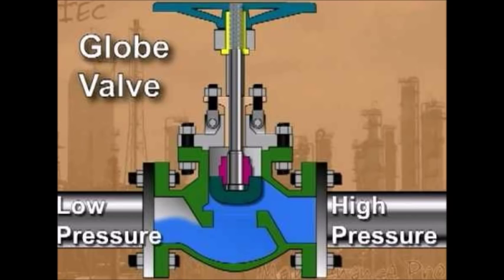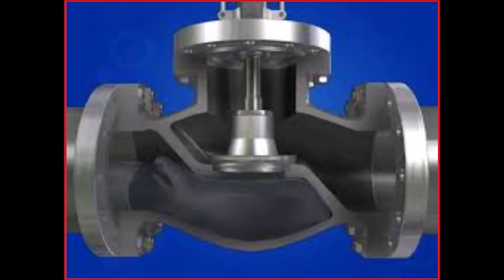With a smooth stem the ends are threaded to allow connection to the plug and the actuator. The stem must not only withstand a large amount of compression force during valve closure, but also have high tensile strength during valve opening. In addition, the stem must be very straight, or have low run-out, in order to ensure good valve closure. This minimum run-out also minimizes wear of the packing contained in the bonnet, which provides the seal against leakage. The stem may be provided with a shroud over the packing nut to prevent foreign bodies entering the packing material, which would accelerate wear.